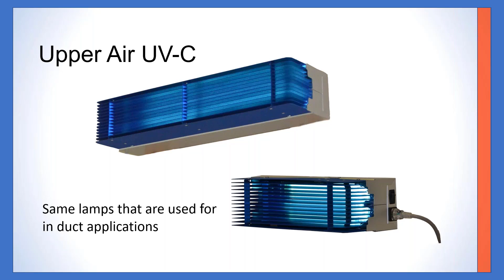These are non-reflective baffles, so they won't reflect that energy — you're collimating the beam that comes out. We've mainly seen them used around patient rooms, but also in daycare centers, lobbies, cafeterias, places like that, and I'll show you some pictures. It sends a collimated beam of UV disinfection across the ceiling, and as the air convects in that room, whether going from supply to return or just natural convection, it rises into the kill zone.